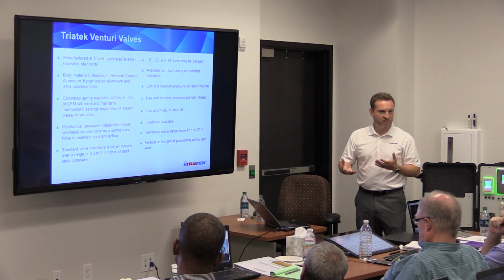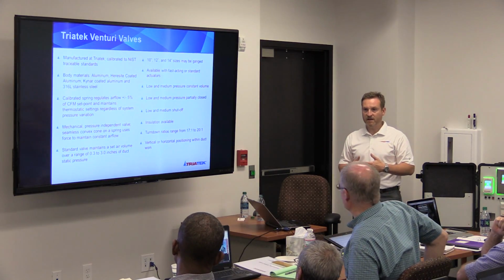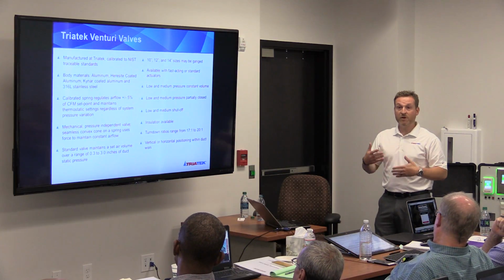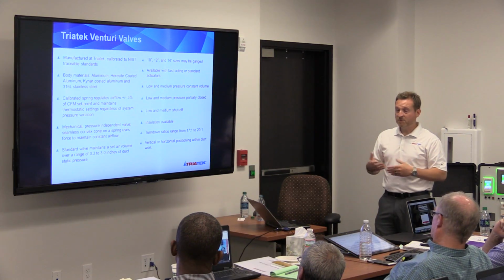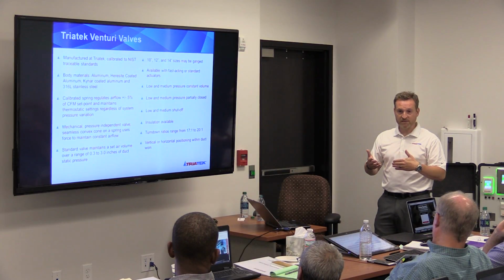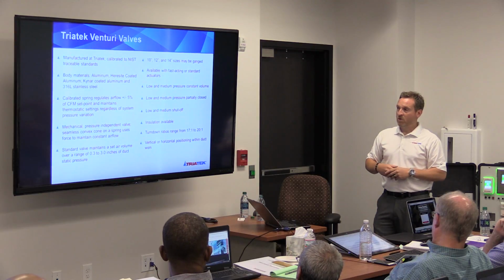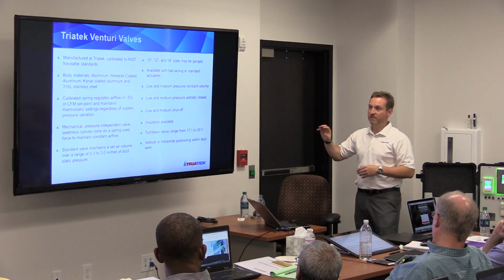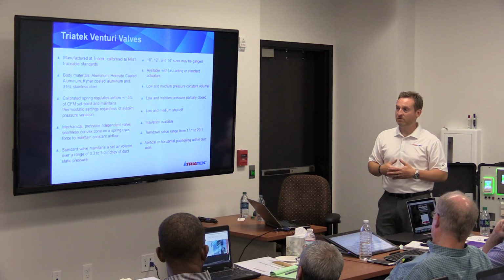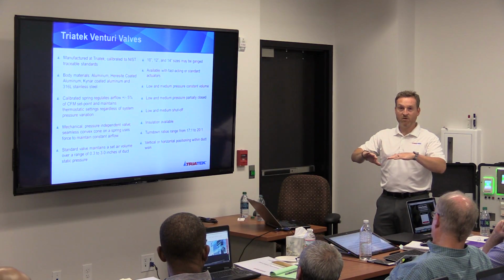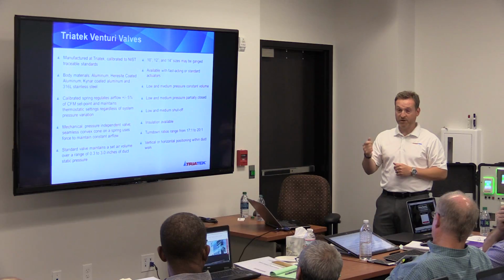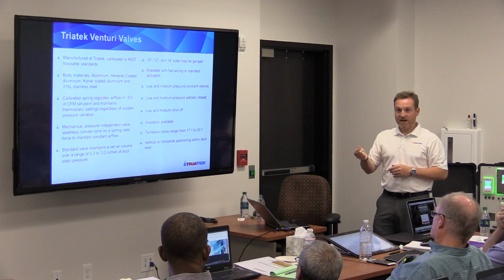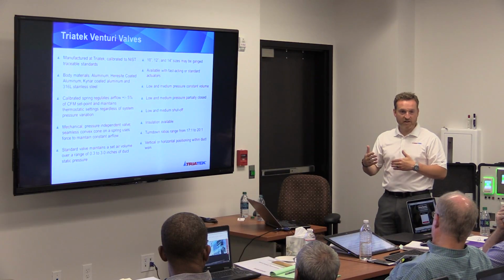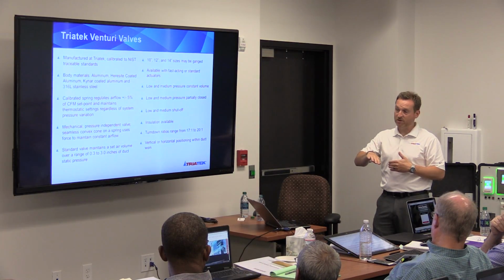Has anyone ever heard of a venturi air valve? Are you familiar with those and how they work? Okay, so for those of you that are not, typically in an HVAC world, you're using VAV boxes or dampers to control your temperature and your heat and your airflow, right? Well, in the critical spaces, you have to maintain proper pressurization. You've got to do it with very minute control and high-speed control. And also accuracy. The VAV boxes are not as accurate, particularly down at the minimum airflows.